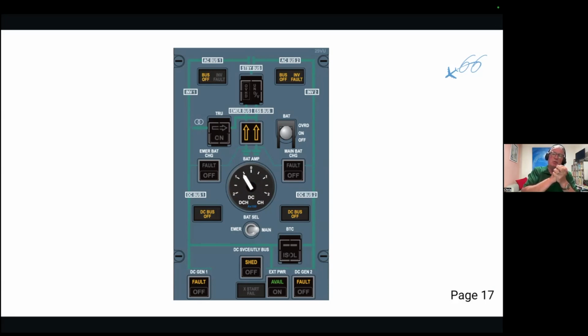However, if there was a situation where the battery was beginning to be defective, then the discharge - the battery would be losing more power than we're adding to it - and therefore this discharge would go into a negative figure, and we'd have to then troubleshoot it as engineers to find out what the problem is, because the batteries on this, they have to work.